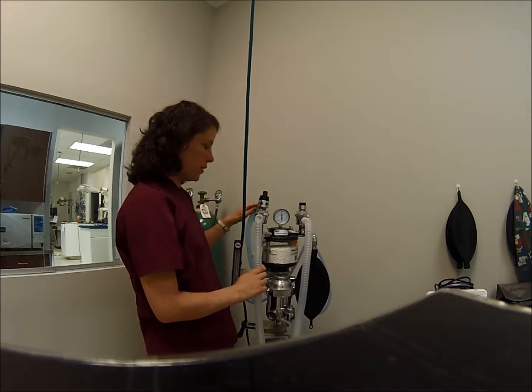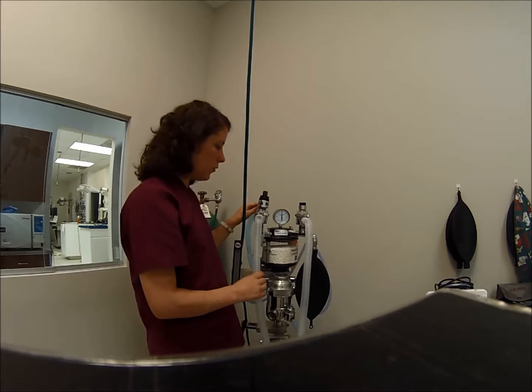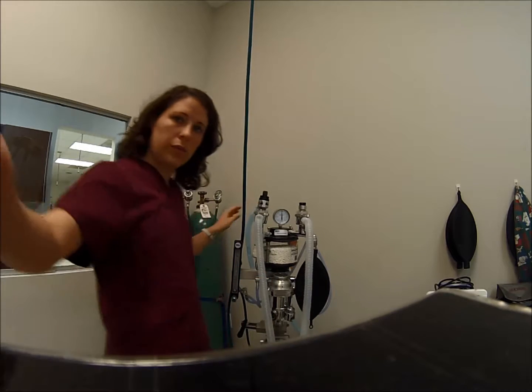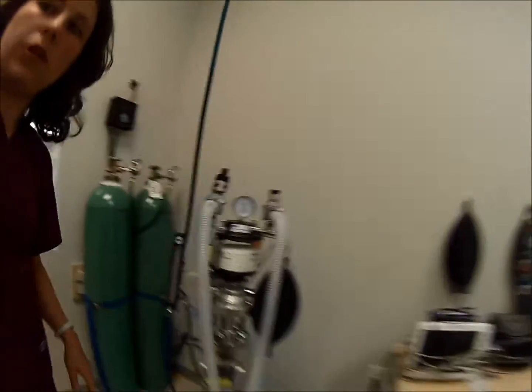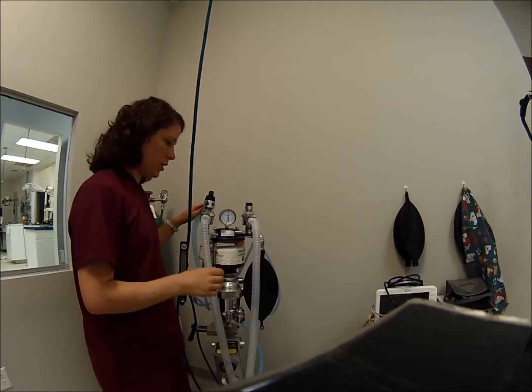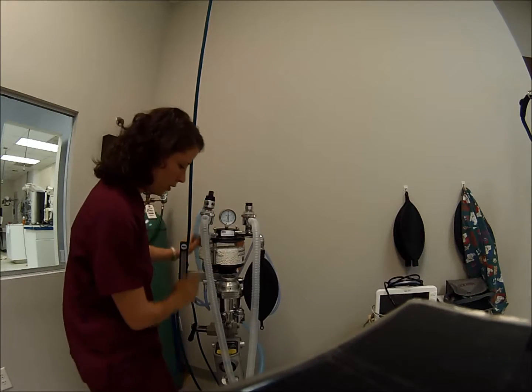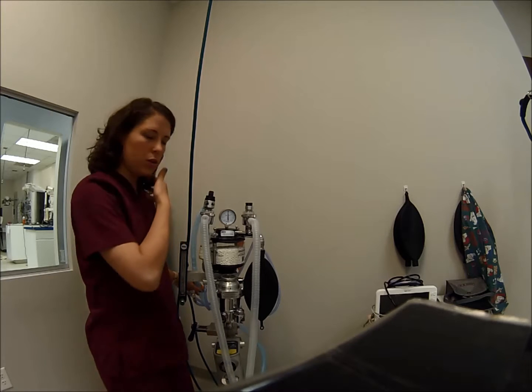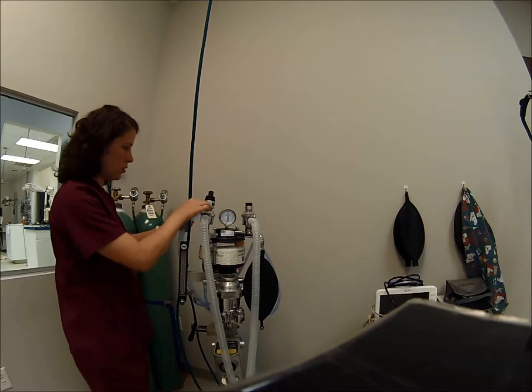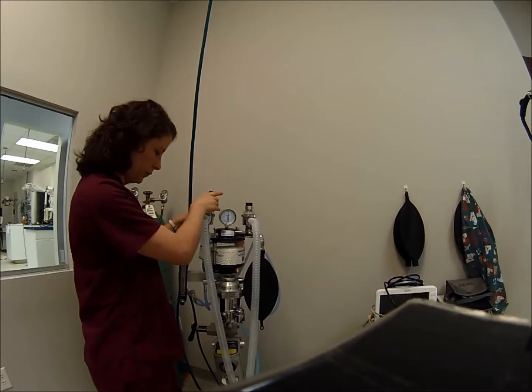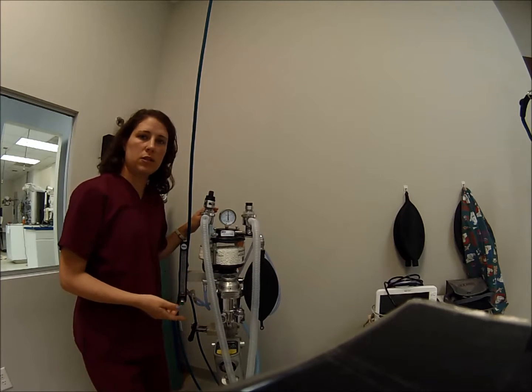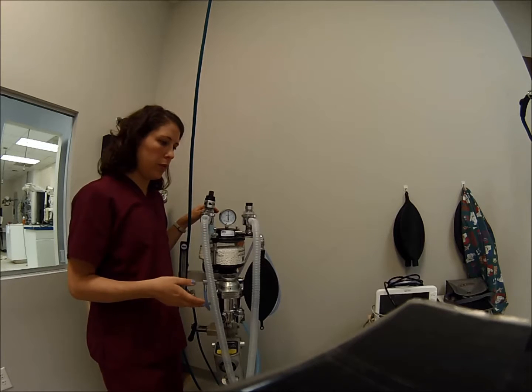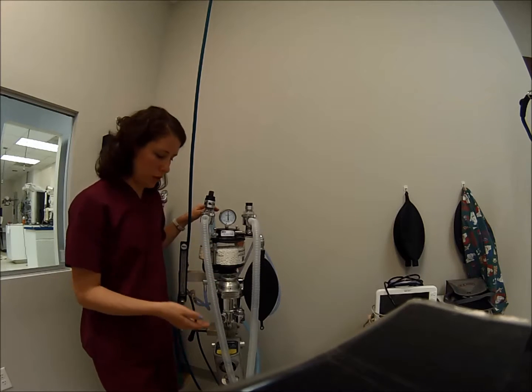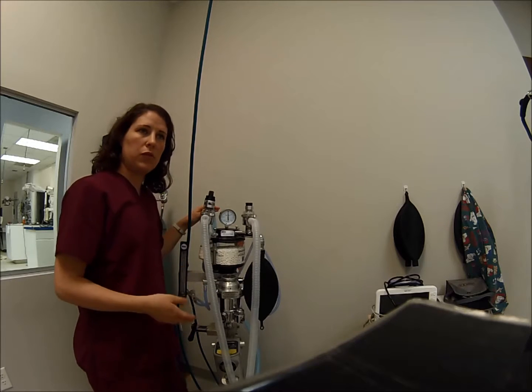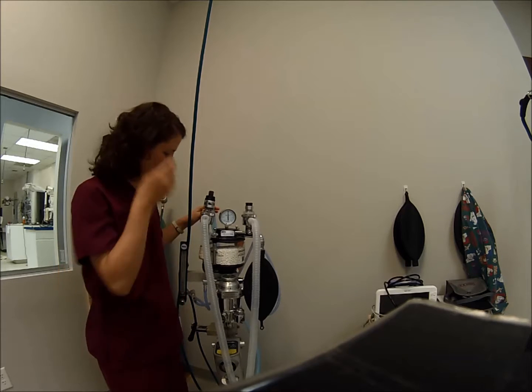Our scavenging system in this practice is passive. We have a canister at the bottom here that relies on gravity to take the heavy anesthetic gases and bring them down into the canister, into the activated charcoal. My exhaust tubing is hooked up to my pop-off valve here. To make sure your scavenging system is working correctly, you'll always want to periodically measure your canister, and when it gets to about 50 grams, you'll want to discard and get a new one.